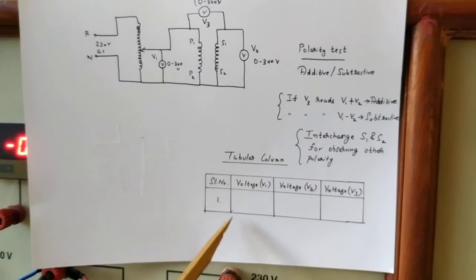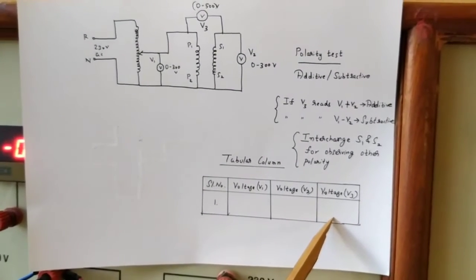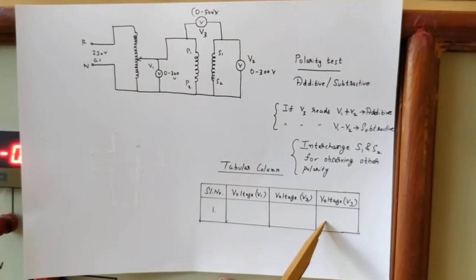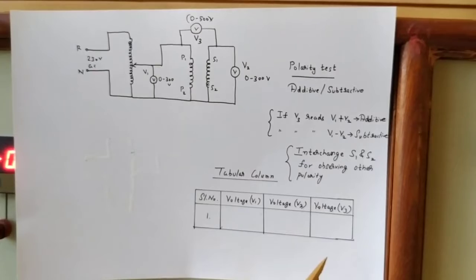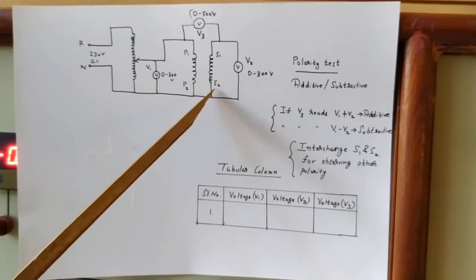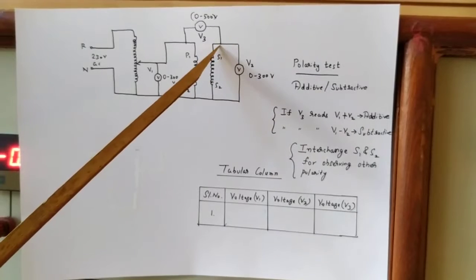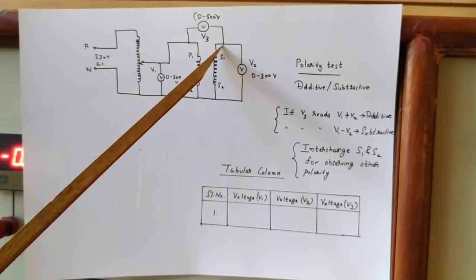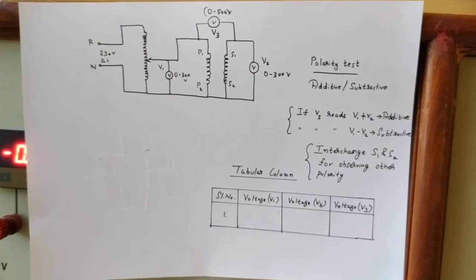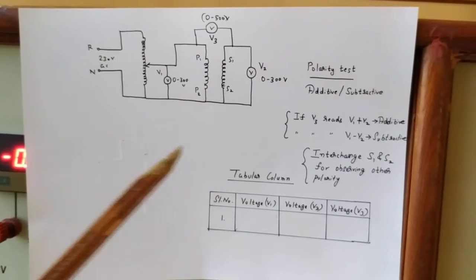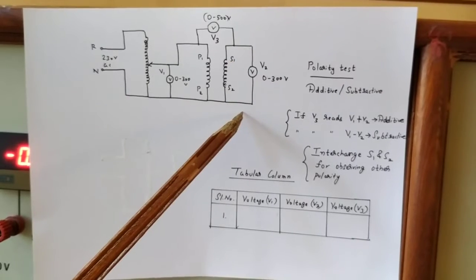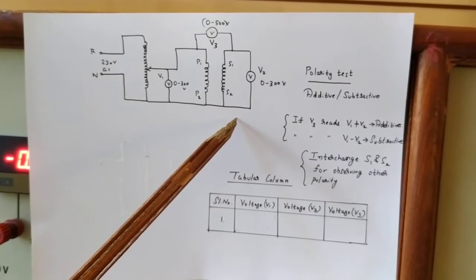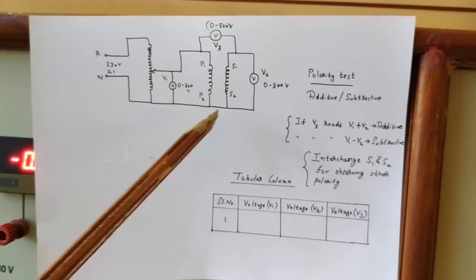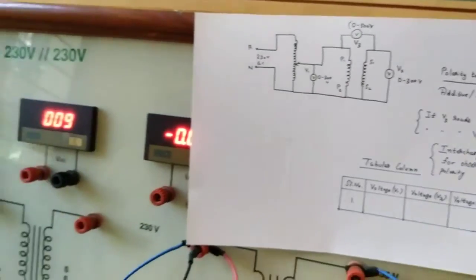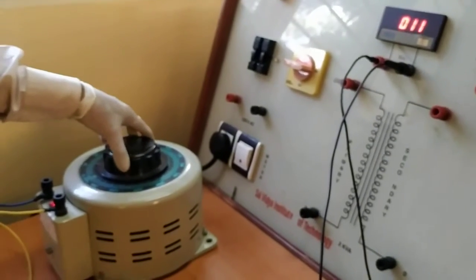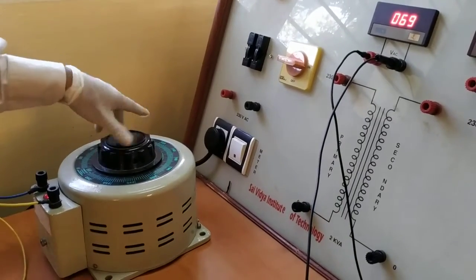The readings V1, V2 and V3 should be noted down in the tabular column. Now since we have observed subtractive polarity, if we need to go for additive polarity, we just have to interchange the terminals S1 and S2. After interchanging them, follow the same procedure. Slowly vary the auto transformer from the initial 0 position up to the rated voltage, which is 230 volts.